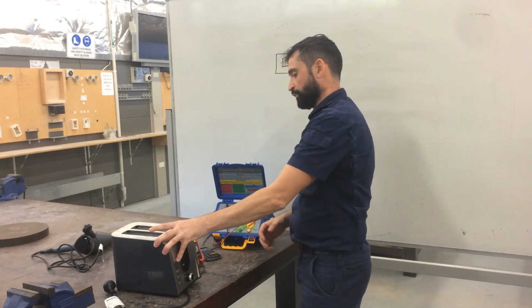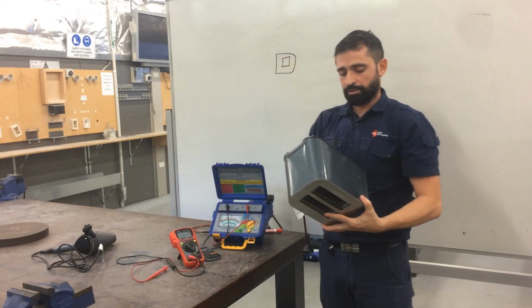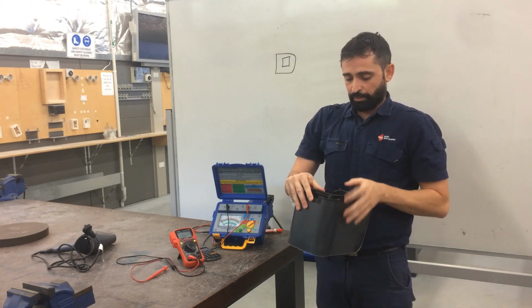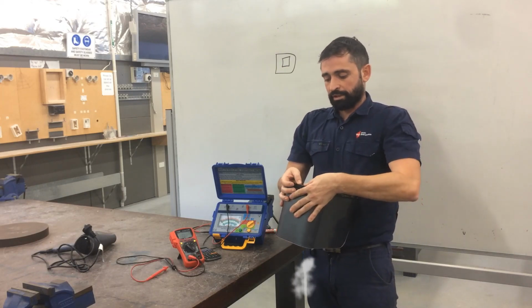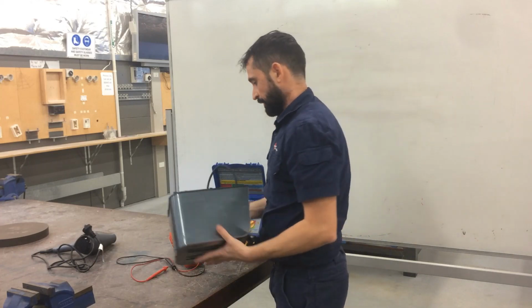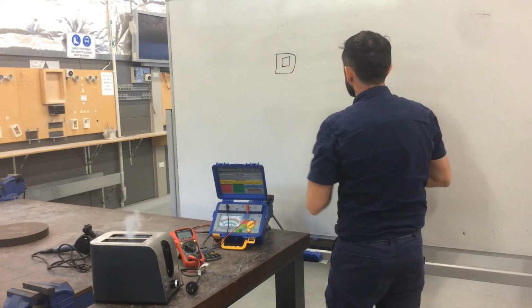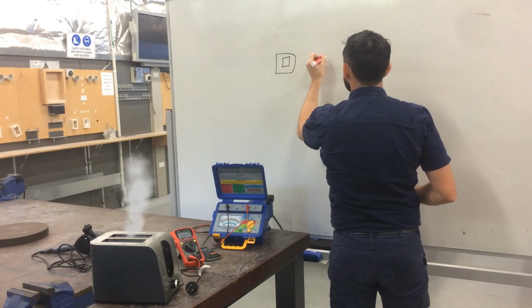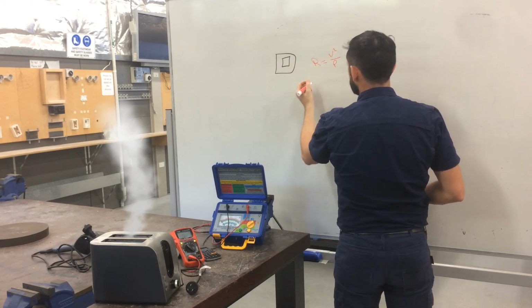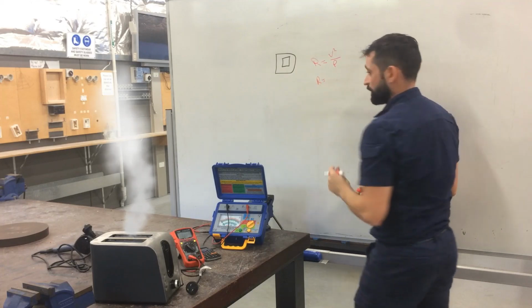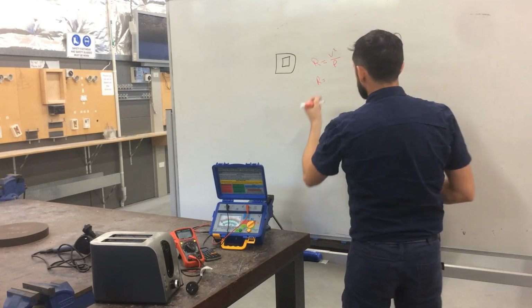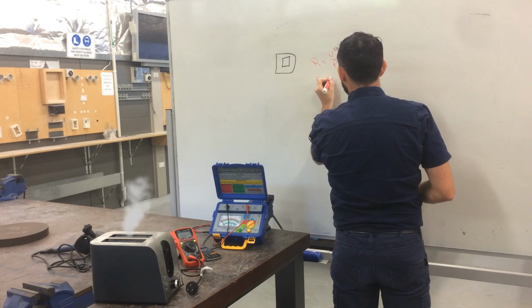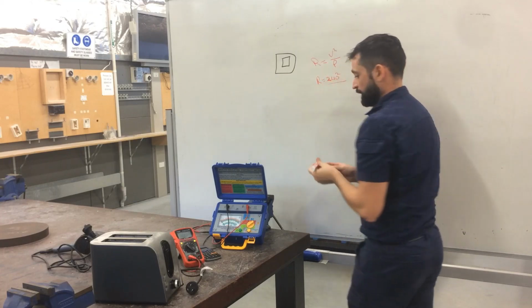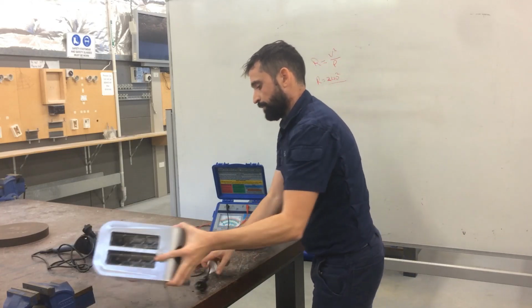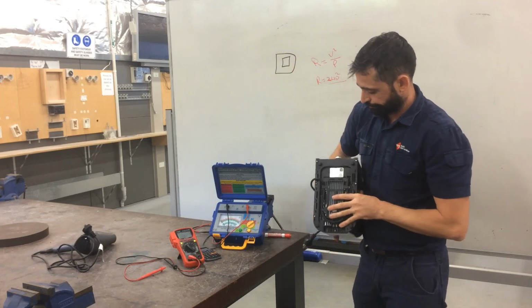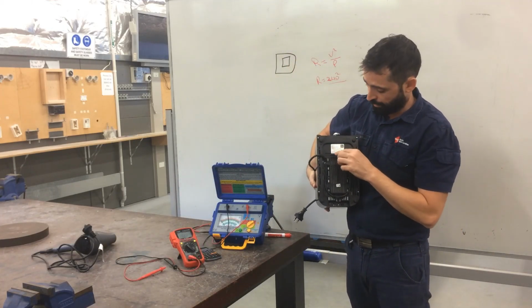What the resistance functional test is, we're basically going to use a power formula with the figures that we're given here in this toaster to work out what the resistance should be if it works correctly. The power formula that we're going to be using is R equals V squared over P. We already know V is going to be 240 volts because that's what we use in an installation. So R equals 240 squared divided by P. Now we simply find P by looking at the base of the unit, usually a nameplate, with any specifications on it.